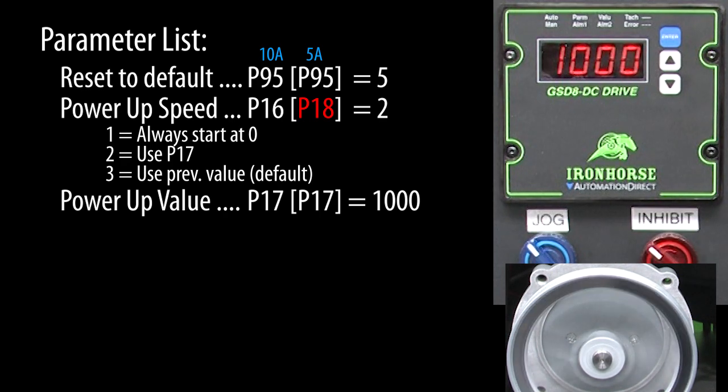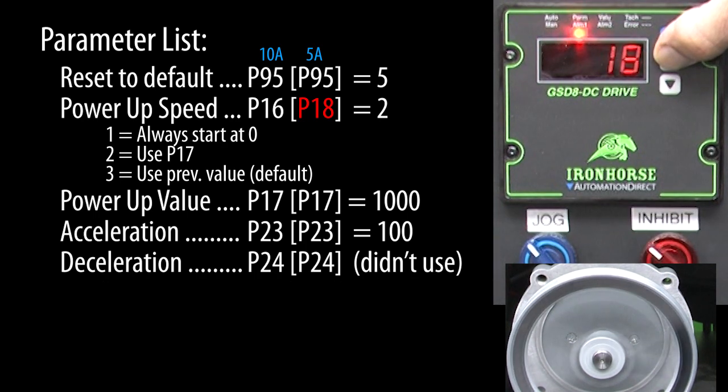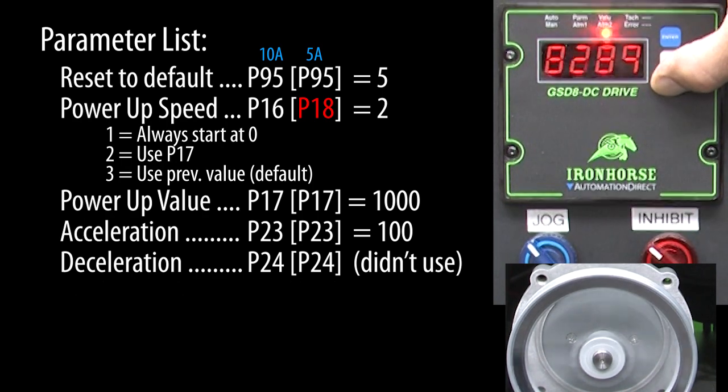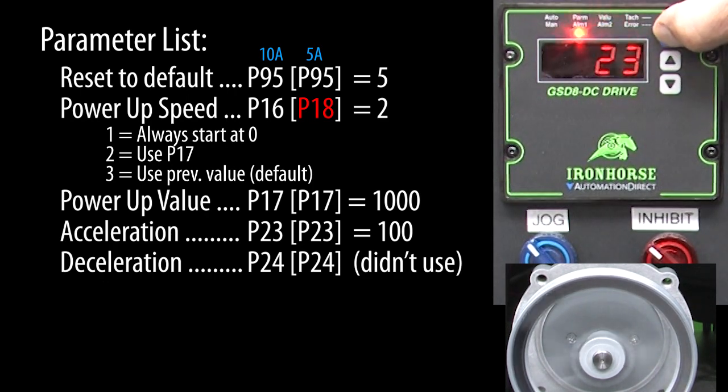We got our rate set. How about the acceleration and deceleration? Those are in parameters 23 and 24. Hold down the enter button for 3 seconds, scroll to parameter 23, hit enter. This is in engineering units per second, which for us is RPM. The 9999 says ramp up as fast as possible. We are running the motor at 1000 RPM, so if we say we want to accelerate at a rate of 100 RPM per second, it should take 10 seconds to ramp up to speed. Enter to accept that.